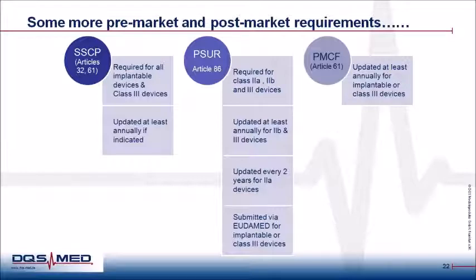The second important report under the pre-market and post-market requirements is the so-called PSUR. PSUR is abbreviated as Periodic Safety Update Report. This is necessary for manufacturers of Class 2A, 2B, and Class 3 devices and must be prepared for each device and, where relevant, for each category or group of devices, summarizing the results and conclusions of the analysis of the post-market surveillance data gathered during the entire life cycle. As per the EU MDR Article 86, the periodic safety update report must be prepared throughout the lifetime of the device. After it has been released to the market, manufacturers of Class 2B and 3 devices shall update the report at least annually, and manufacturers of Class 2A devices shall update the report at least every 2 years.